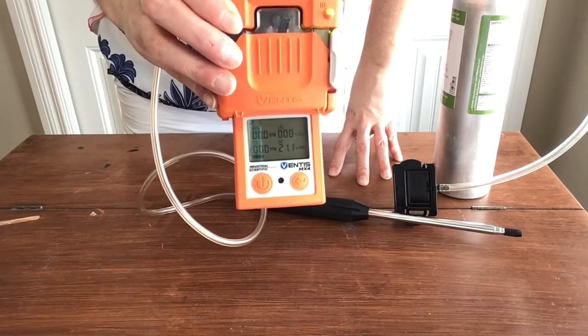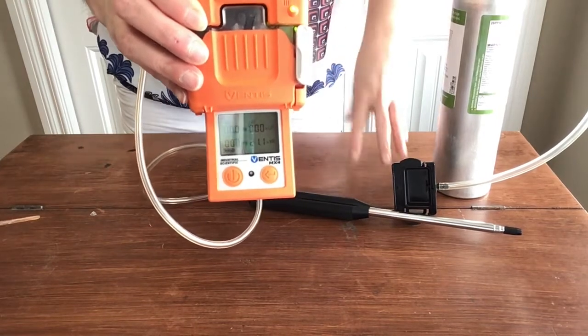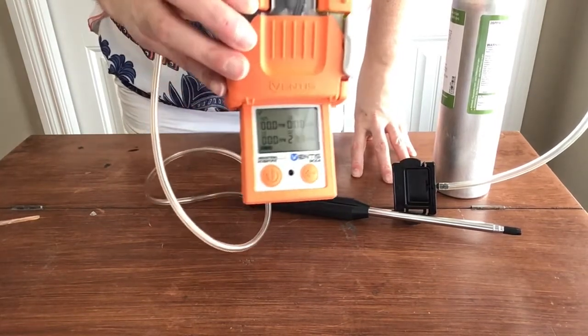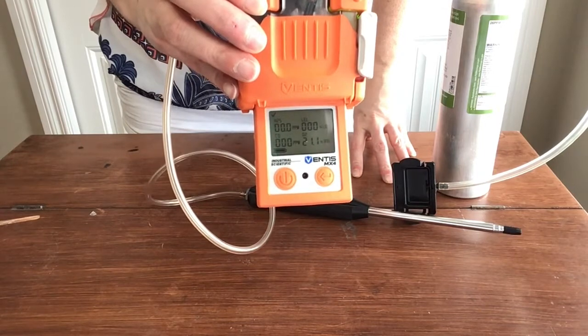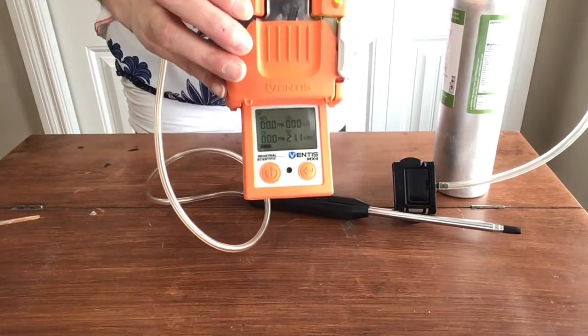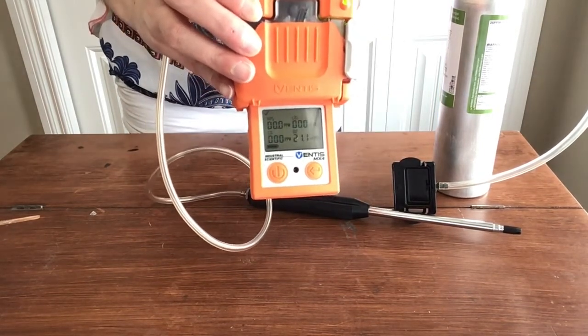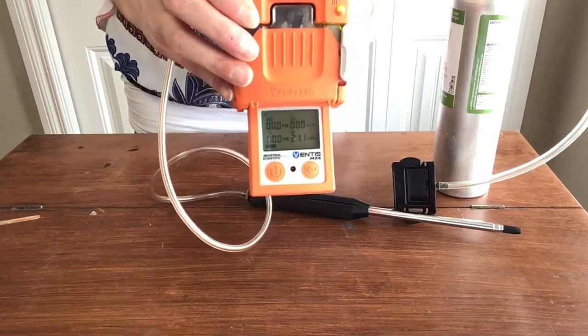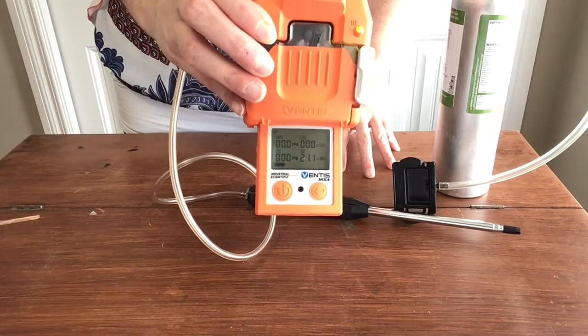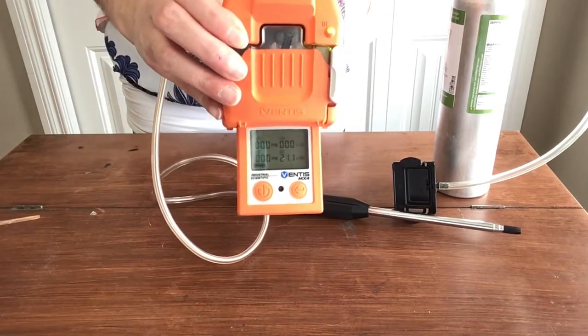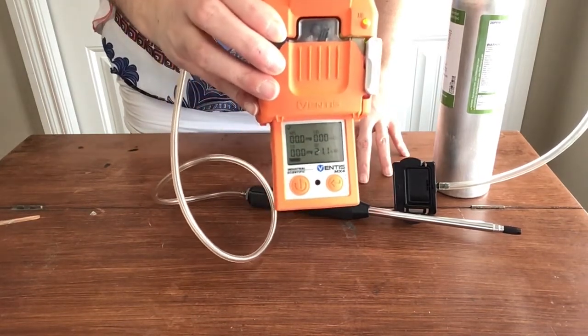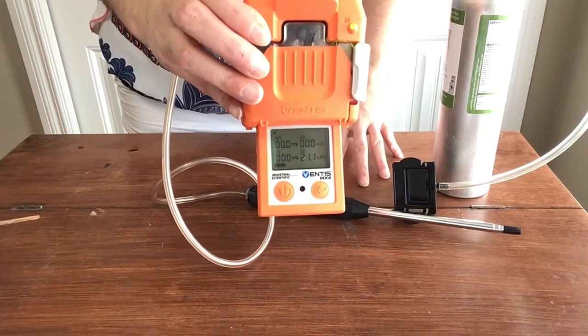And you want to be reading, there's recommendations in the CSA standard as to how to do your confined space monitoring to make sure that you're monitoring top, middle, bottom, and at sufficient intervals to ensure that you're checking the entire atmosphere as a whole and that you're not missing any areas where gas may be sitting, or areas that could be oxygen deficient, right? So that's pretty much it.